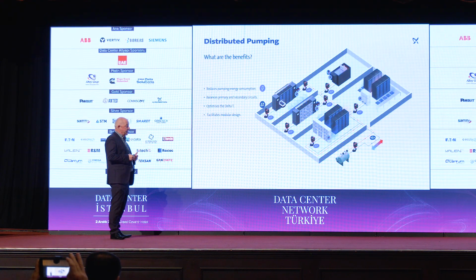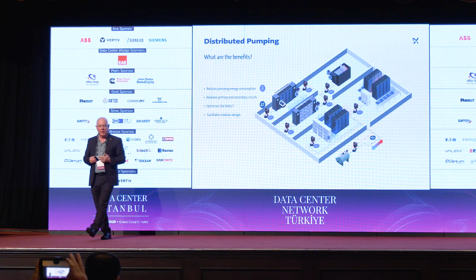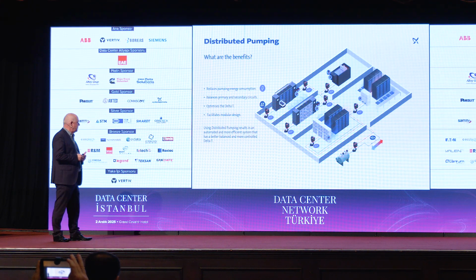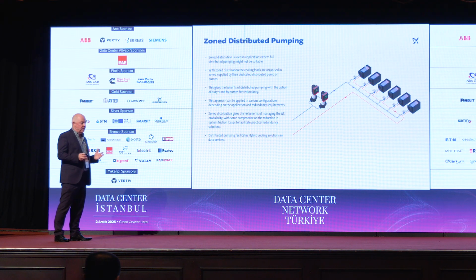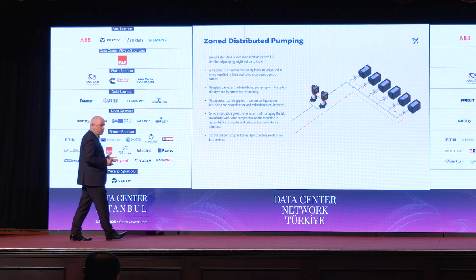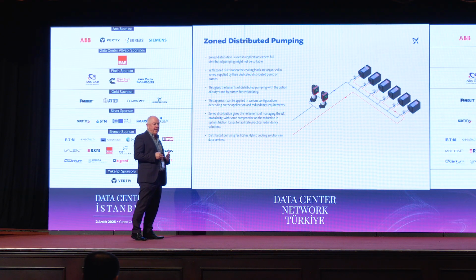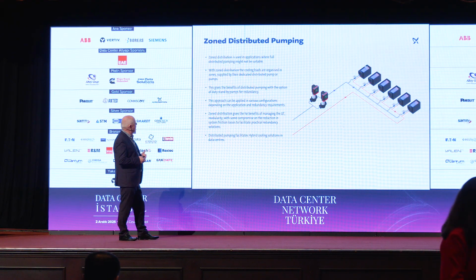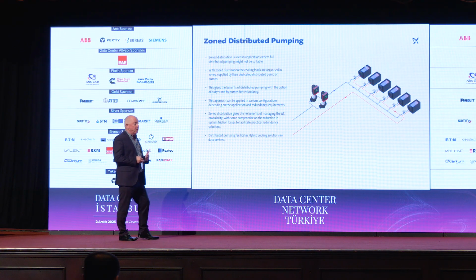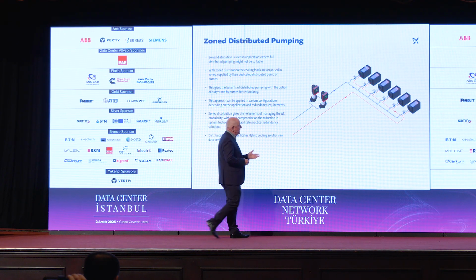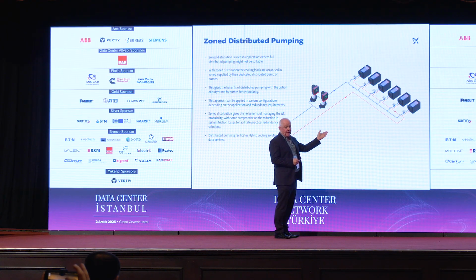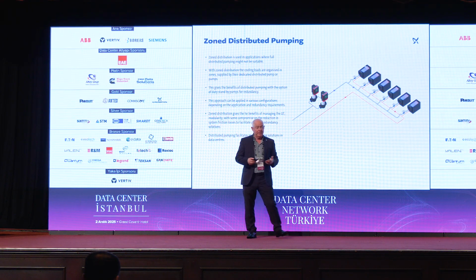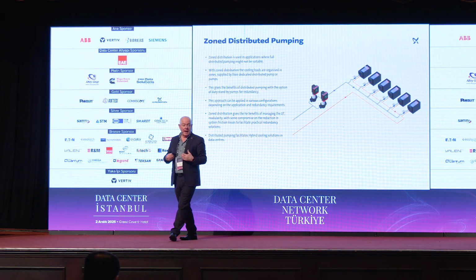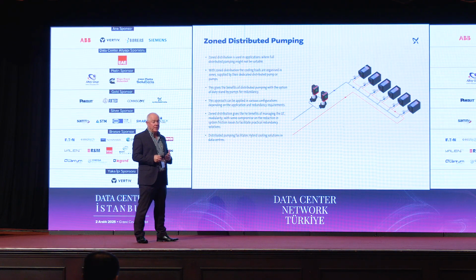And as I mentioned, modular design is very workable with modular systems. So if we had a look at a system and we've a lot of small loads, or for some reason we can't use a full distributed system, we can look at zone distributed systems where we take groups of cooling loads, and we're showing liquid cooling here, immersion cooling. It could be fan walls, or it could be CRAH units or whatever, and we would group them together, particularly if they're small loads, and we would put a pumping system in then to distribute to them.